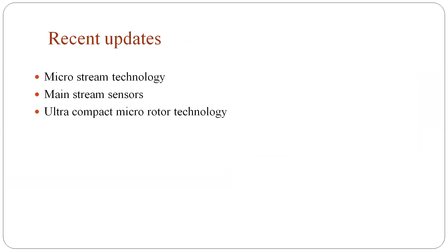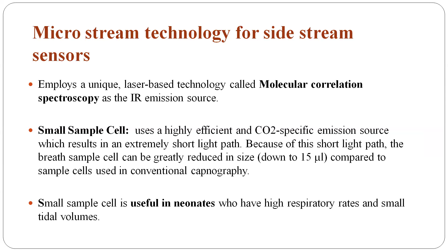Coming to recent updates: microstream technology, mainstream sensors, and ultra-compact micro-rotor technology. Microstream technology is for side stream sensors. It employs a unique laser-based technology called molecular correlation spectroscopy as the infrared emission source. It has a small sample cell and uses a highly efficient, carbon dioxide specific emission source, which results in an extremely short light path. Because of this short light path, the breath sample can be greatly reduced in size, down to 15 microliters, compared to the sample cells used in conventional capnography. This small sample cell is useful in neonates, who have a high respiratory rate and small tidal volumes.